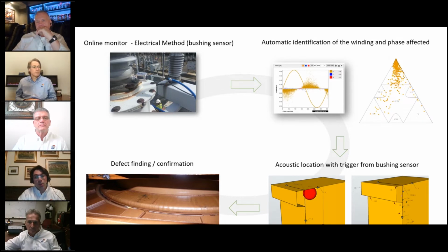So what we did here was install online, permanent partial discharge monitoring systems. This PD monitoring system was installed using electrical-type sensors, connected, as you can see in the slide, at the test tap of the bushing. This is a quite reliable way to detect both the 50 or 60 hertz signals and the partial discharges, correlate them, and also do some intensity evaluation in volts peak or nanocoulomb in the field.